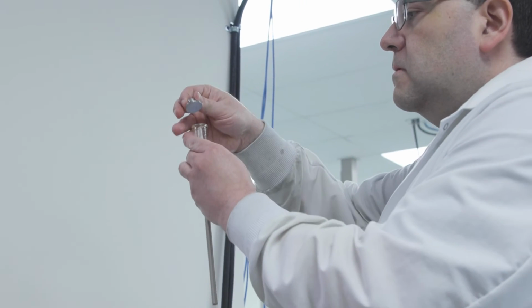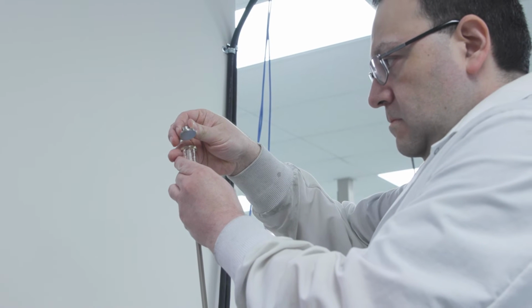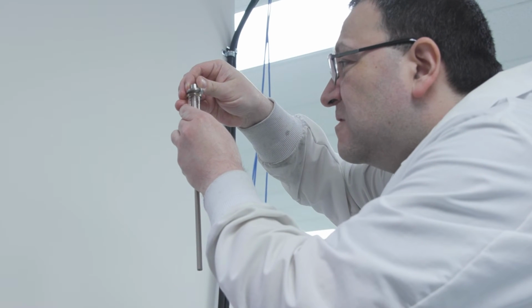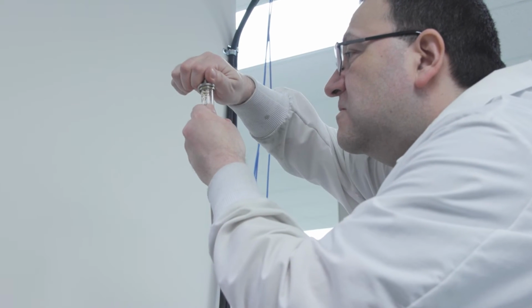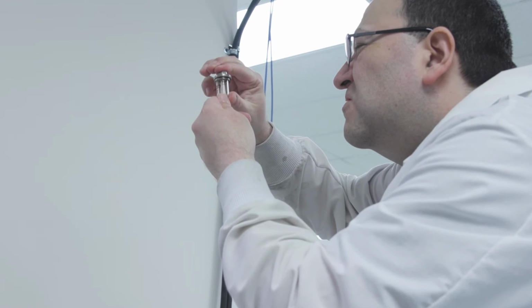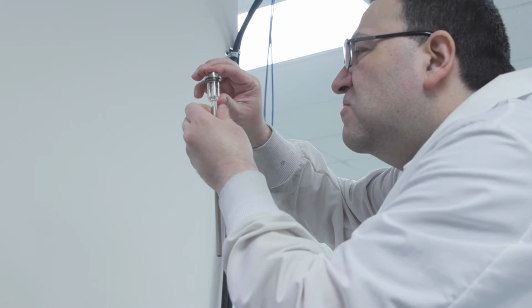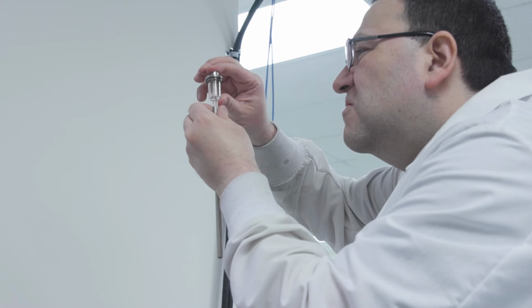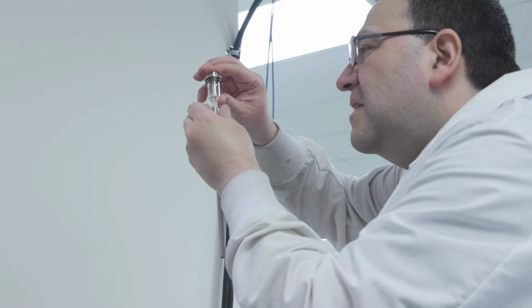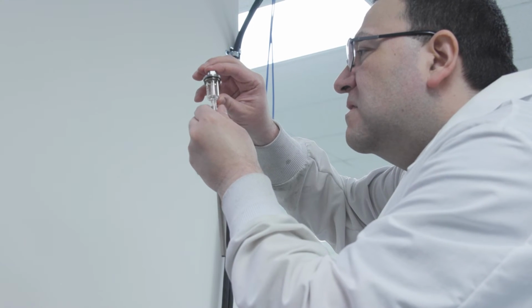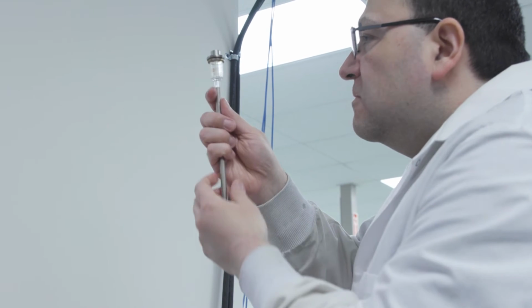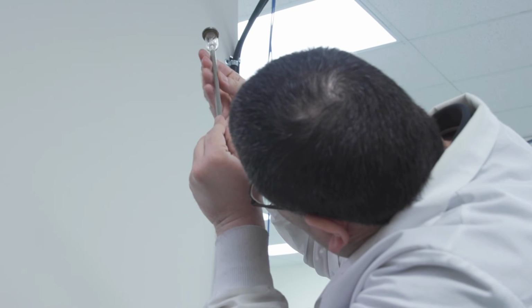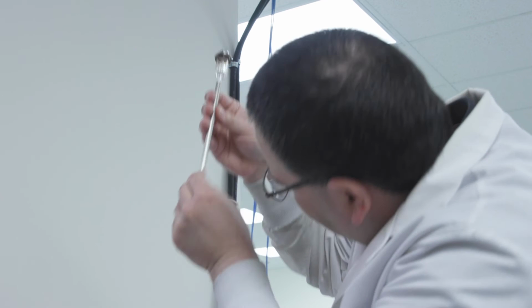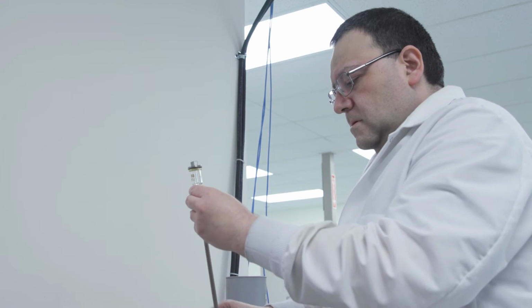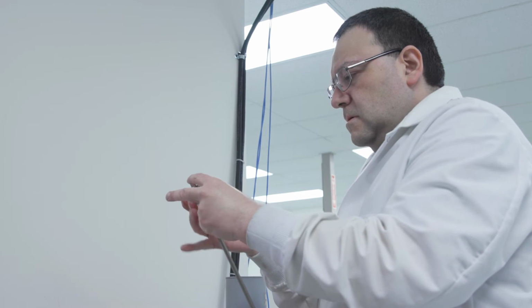And then applies the cap, being careful to align it to the top of the sealing surface. He verifies that the cap is properly aligned on top of the penetrometer and checks for a uniform seal by looking through the penetrometer at the sealing surface. Now he adds the sealing nut and tightens it snugly.